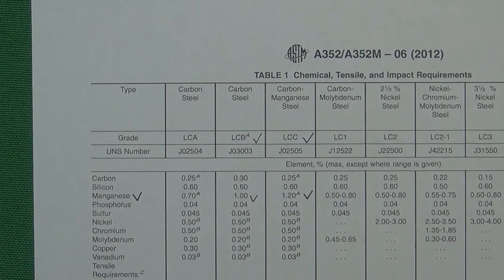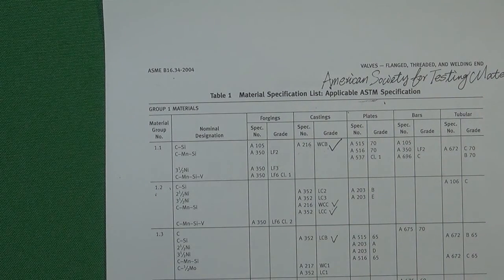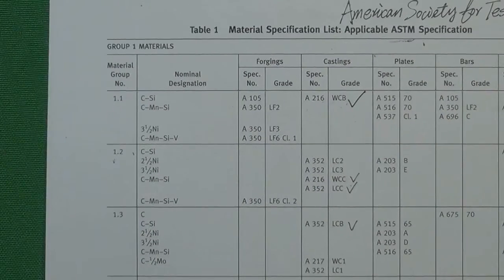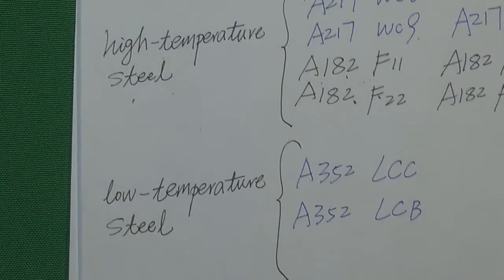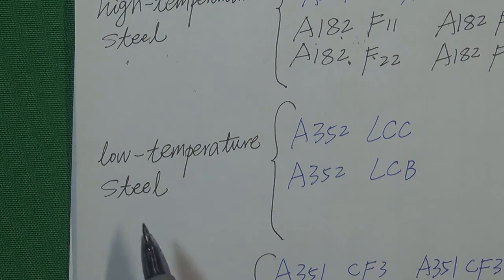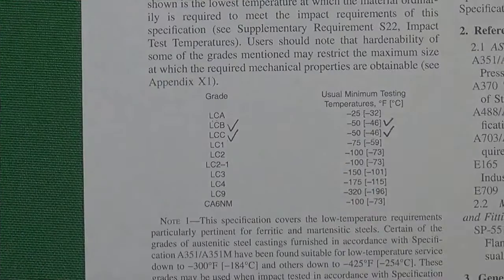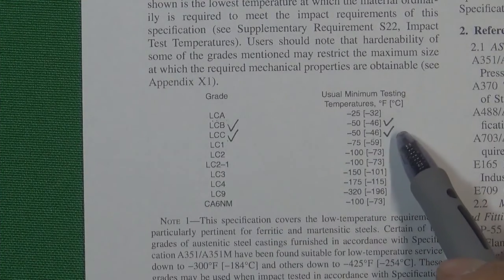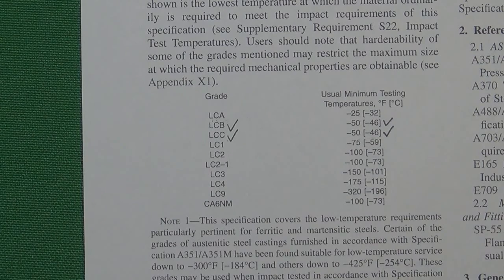According to the standard ASME B16.34 material specification list, this kind of material does not have a forging form — LCC and LCB are casting form only. That is why there is no separate forging standard listed for low temperature steel. In the low temperature steel group, it just contains the standard A352 for casting low temperature steel. The standard tells us that LCC and LCB's minimum temperature is minus 46 Celsius degrees, which equals minus 50 Fahrenheit degrees.